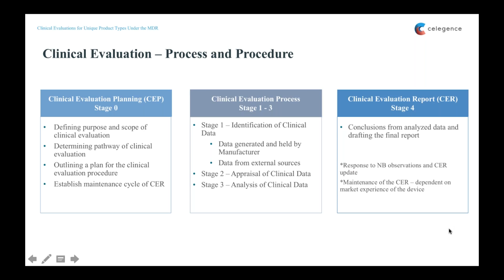After submission of the CER to the notified body, there may be observations from the reviewers which need to be addressed. The CER also is a live document that needs periodic updates. The frequency of these updates will be dictated by the risk category of the device and the post-market experience. For example, identification of a new risk from the PMS data may instigate an update of a CER.